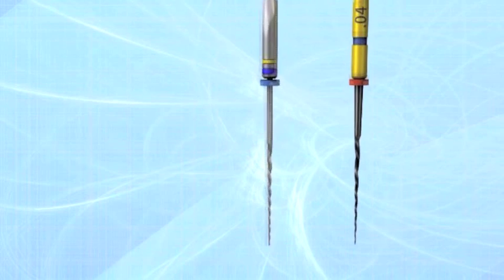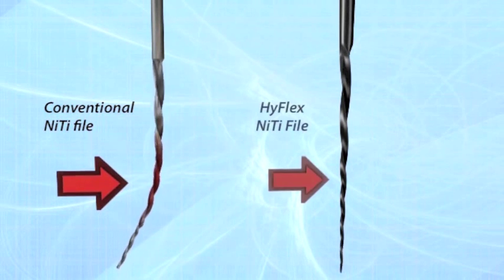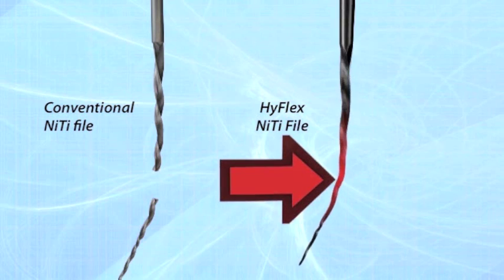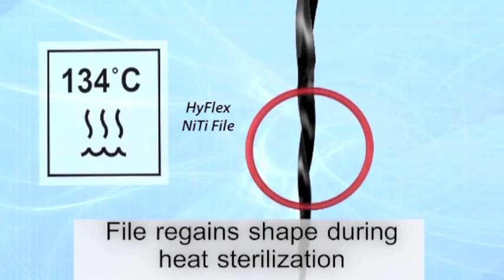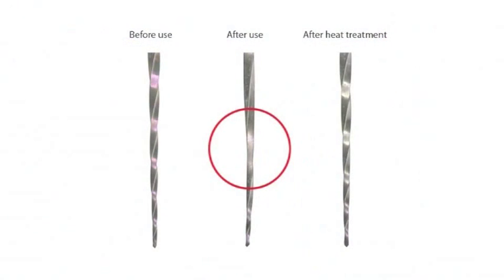HyFlex CM NiTi files respond to excessive resistance with straightening of the spirals, which avoids binding to the walls and therefore increases fracture resistance. This form adaptation can be reversed quickly by heat treatment, during autoclaving or with a glass bead sterilizer, returning the instruments back to their original shape.